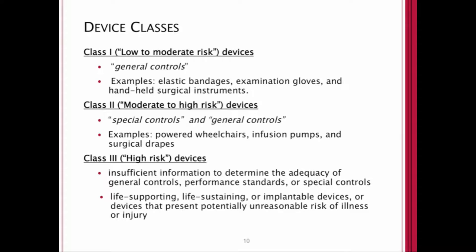Class one devices are considered low to moderate risk — examples include elastic bandages, examination gloves, and handheld surgical instruments. Class two devices, considered moderate to high risk, require special and general controls — examples are powered wheelchairs, infusion pumps, and surgical drapes. Class three is the highest risk class, where either there is insufficient information to determine the adequacy of general or special controls, or these devices are life-supporting, life-sustaining, implantable, or present a potentially unreasonable risk of illness or injury.